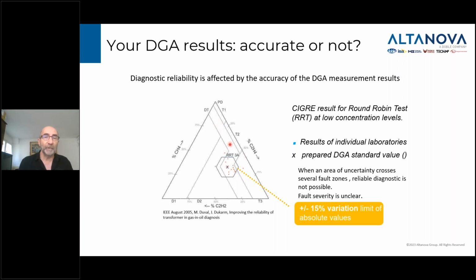So here it tells you that, for that particular sample, you potentially have a thermal and a dielectric fault happening. As the accuracy error increases from 0% to, in this example, 15%, the results start moving away from that optimum diagnostic point. You can see the red dot here. The pentagon you can see here tells you the surface of uncertainty in the accuracy measurement and the accuracy of the diagnostic.